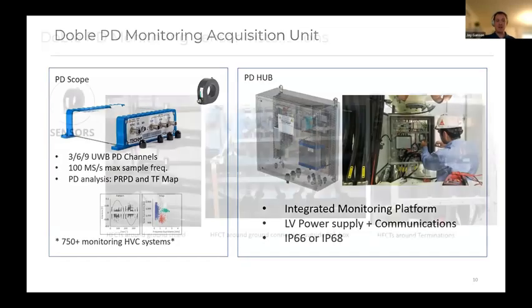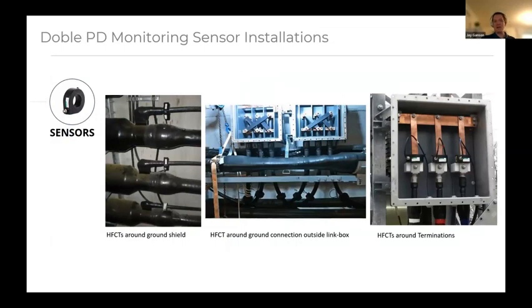The sensors themselves are typically HFCTs that we install on the ground leads coming off of the splice. So here in this picture, you can see highlighted in red different examples of where we would attach our sensors to the grounds. Oftentimes we can do that right in front of the cross-link or cross-bonding link box. But we can gather all of this data and provide real-time asset health information on the health of the cable using PD. Now, something that we're experimenting on, or not experimenting, but we're actually deploying today, is the infrastructure to do PD monitoring and continuous monitoring on underground cable is sizable. And while we're there, we're looking at what other things we can bring into monitoring that address the total cost of operating a system. So in addition to asset health, how can we bring in operational parameters?